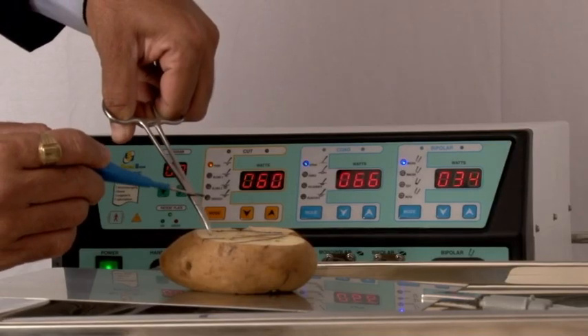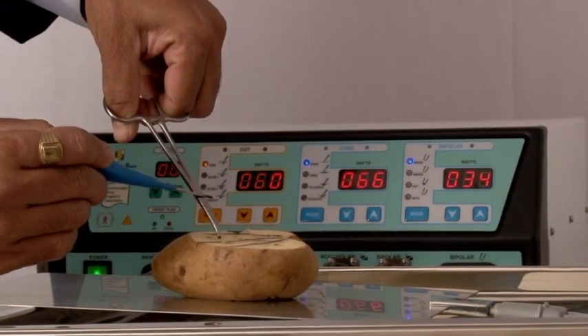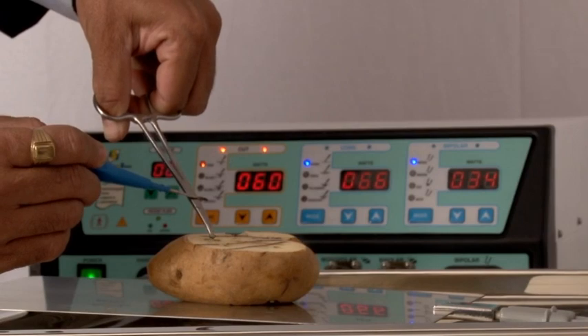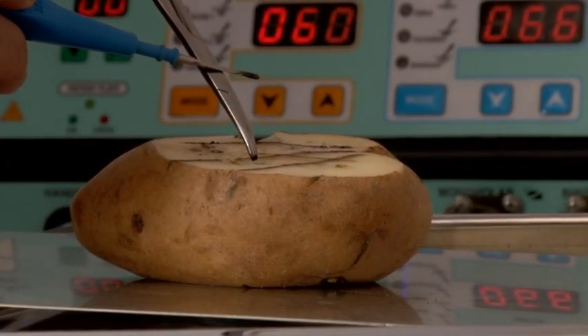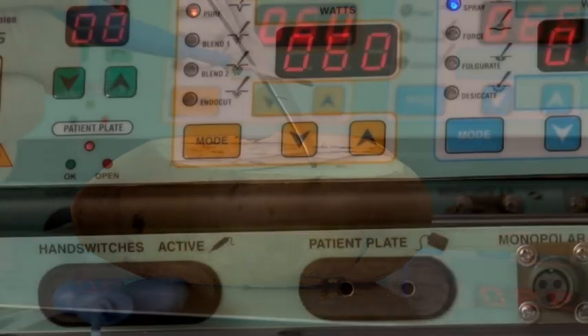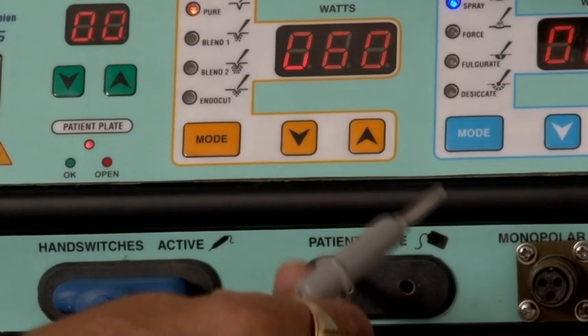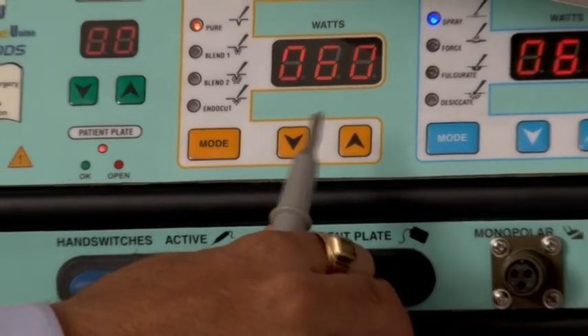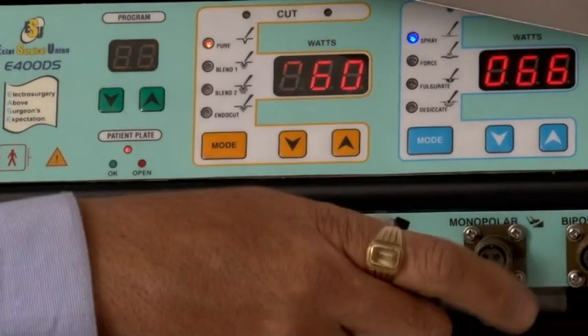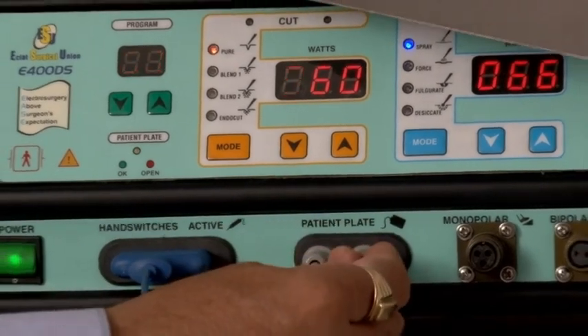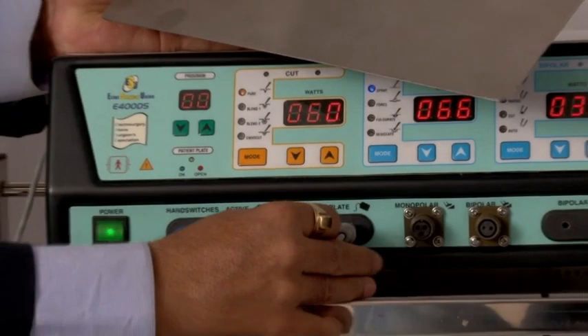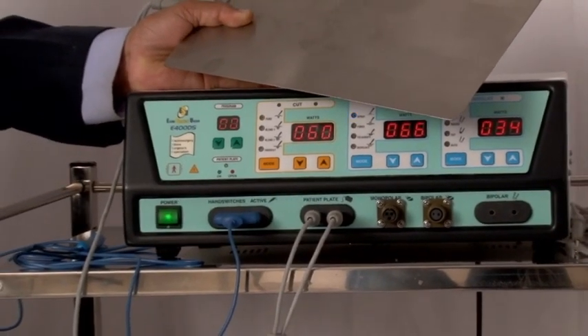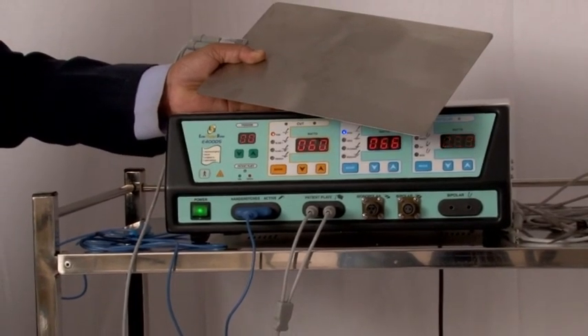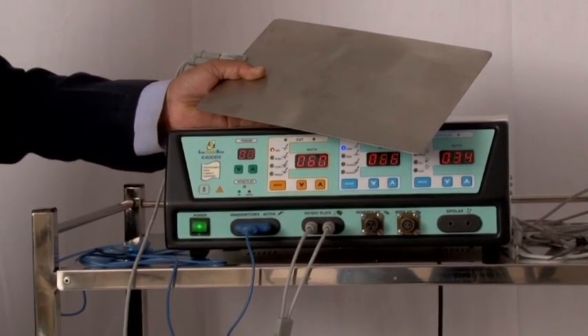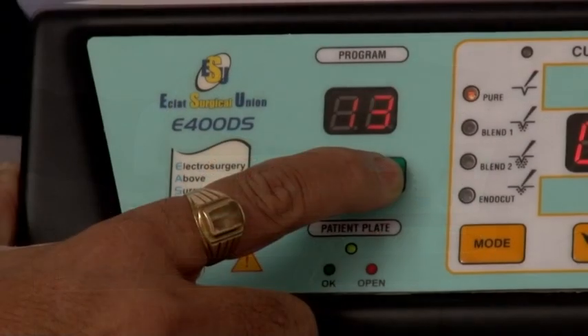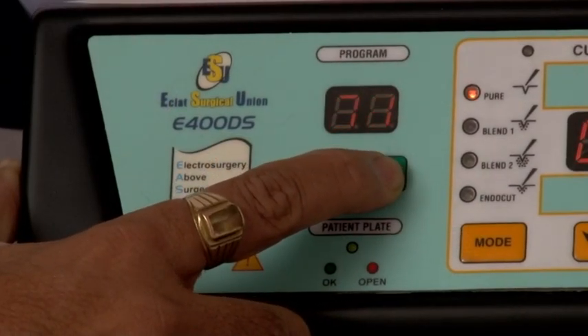An artery forceps held in bare hands without gloves and touched with live electrode proves highest safety standards of our electrosurgical generator. A safety alarm is provided for patient plate. When patient plate is not attached to the machine, it alerts with red light and audio alarm, and it does not allow any output power from electrosurgical unit. Once the patient plate is attached to the machine, it shows green light and machine is ready for delivering the output.